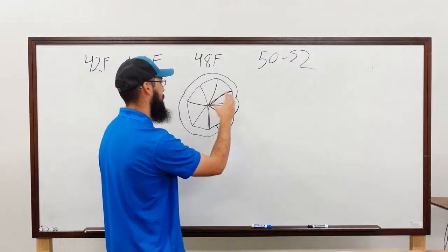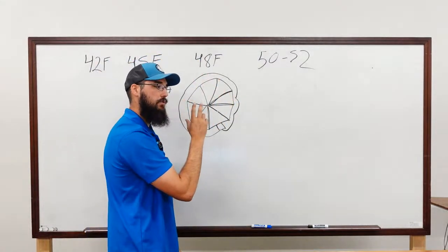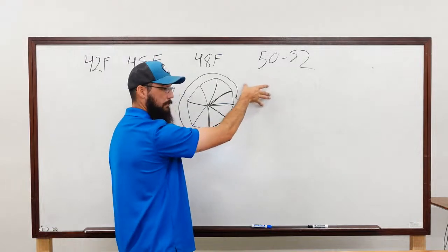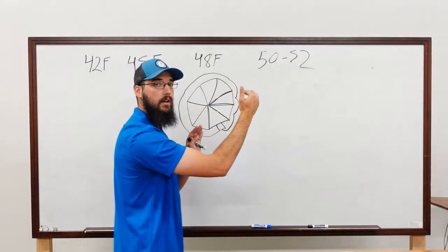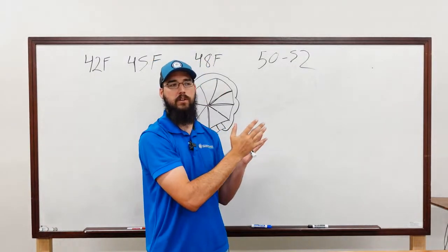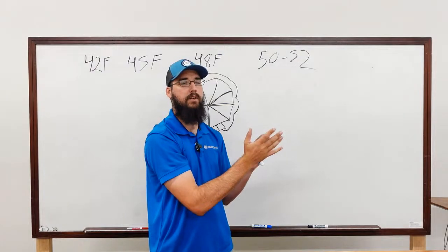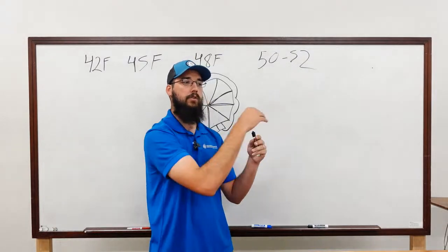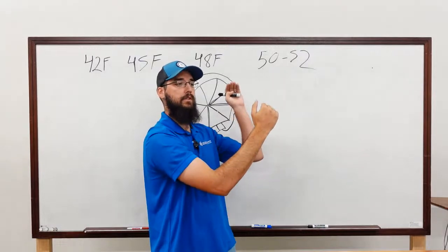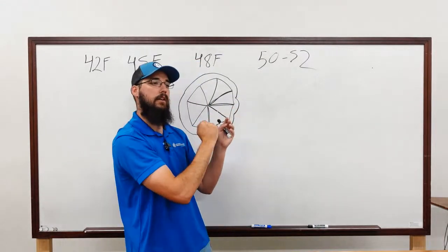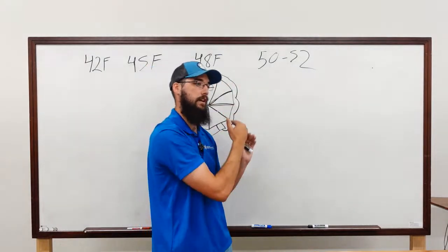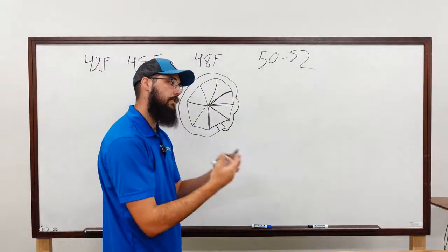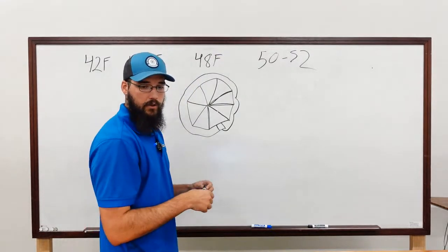Well, let's say our load is coming down, and with the algorithms built into the machine's control and the PID loops, it decides, based off of my surge curve, that it can change speed. There are surge maps for every compressor. I think most of the time you can even request those. I know York specifically, you have to ask for it, and they won't always give it to you. But each compressor has a surge map designed for it, where it's basically your lift, your PRV position, your compressor speed. It's got several parameters built into that. If you get outside of the right side of the graph into more of the left end, you're in surge territory. It's almost like a pump curve. It's a centrifugal compressor's version of a pump curve, honestly. You could think of it that way.